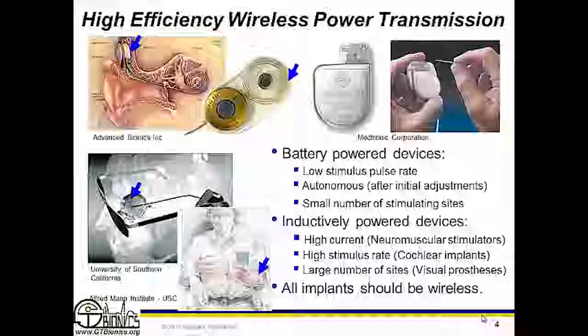So when you average out, the average power consumption of a pacemaker is about, as it was mentioned, in the order of 10 microwatt. Therefore, even though more than half of this can is filled with a battery, that battery is a primary battery that would last in most recent pacemakers for about 10 years. When the period of replacement of this device is in the order of 10 years, the power consumption is so low, you can afford to have a primary battery.